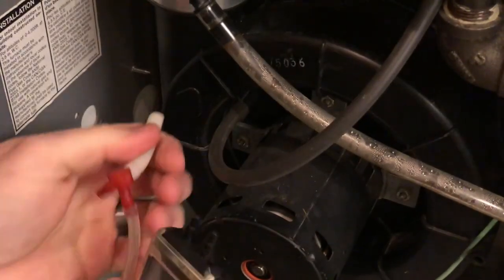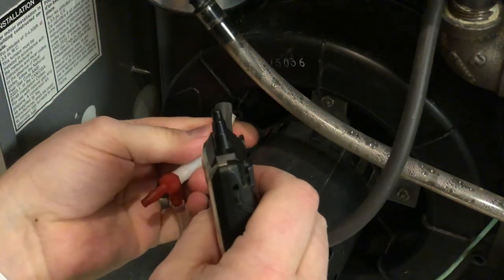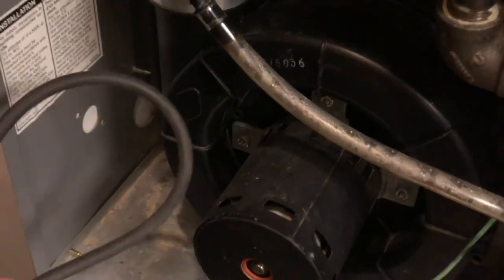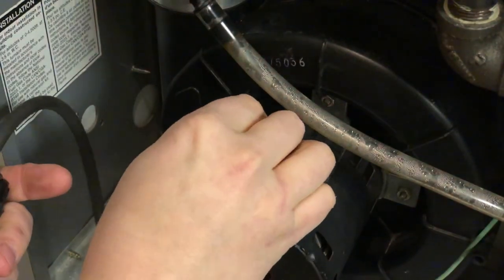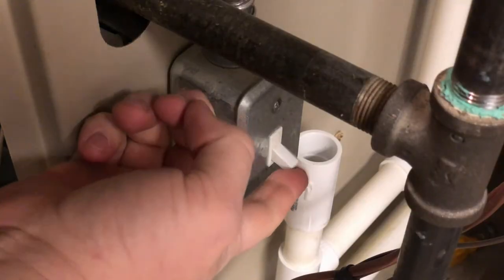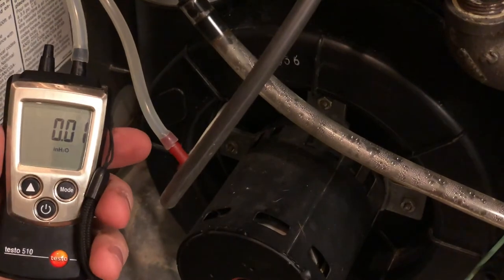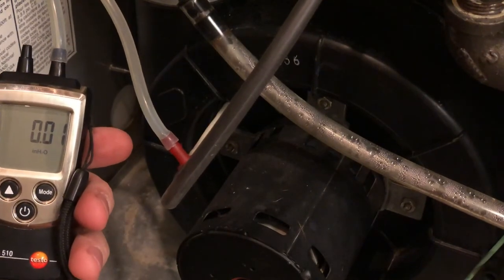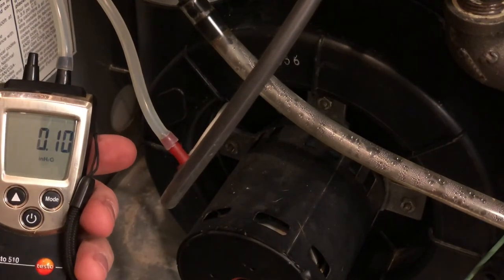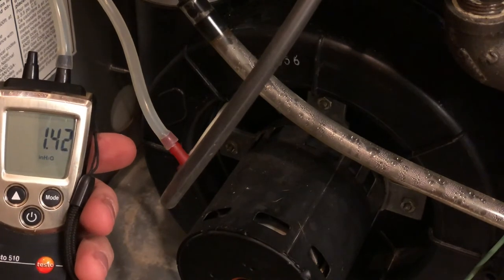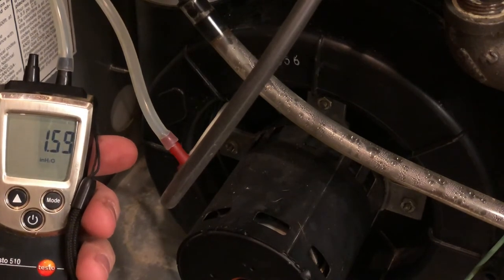Again, connect your manometer to the exhaust tubing with a T, or even directly to the exhaust motor if you don't have a T, and reset the power to your furnace. Watch the pressure rise from 0 inches of water column to hopefully above the pressure switch's rating. If the pressure doesn't ever rise above the pressure switch's rating, then the pressure switch is doing its job, and there's another problem that's causing the pressure switch to not close.